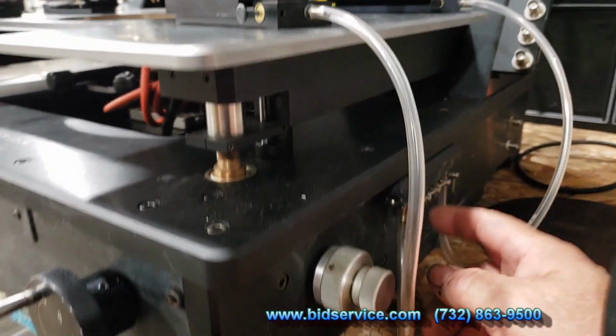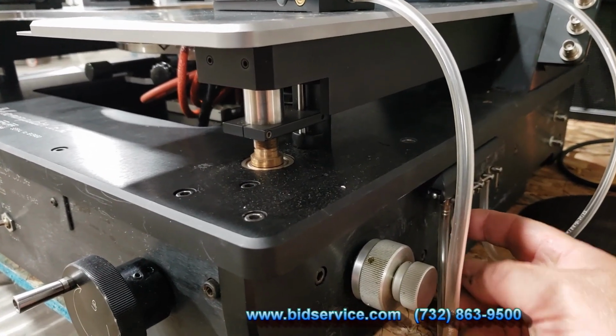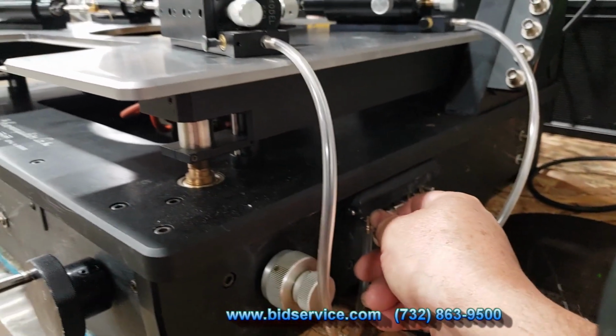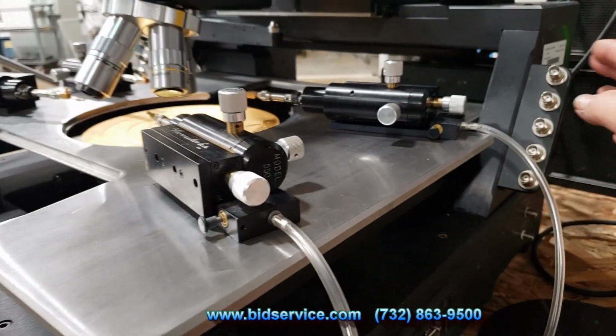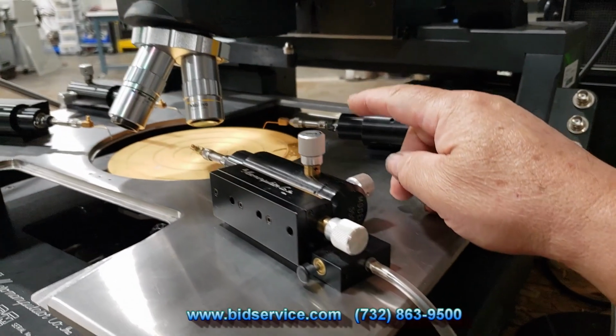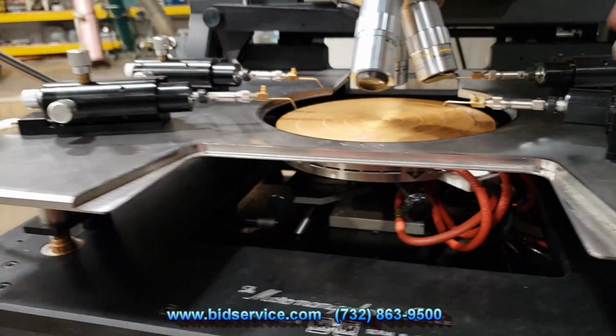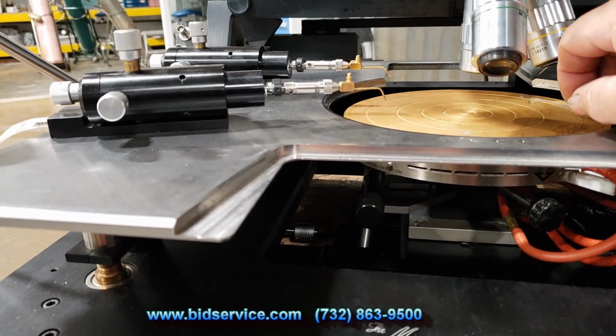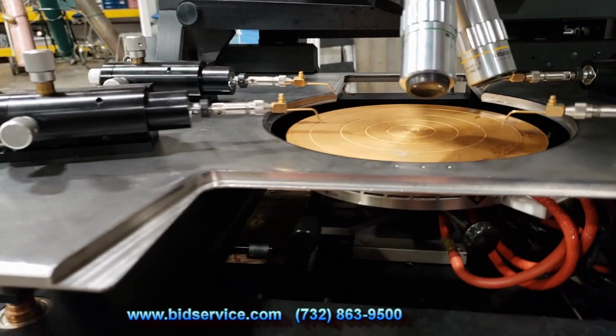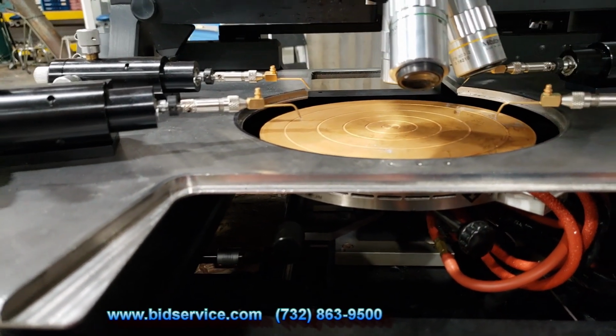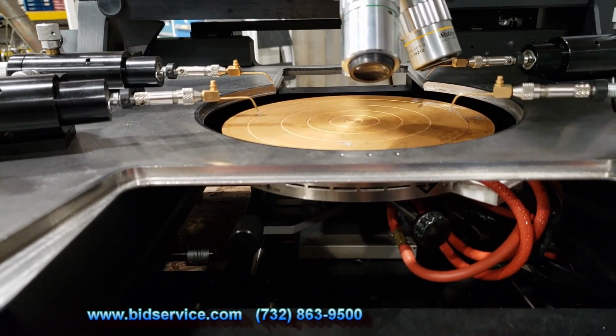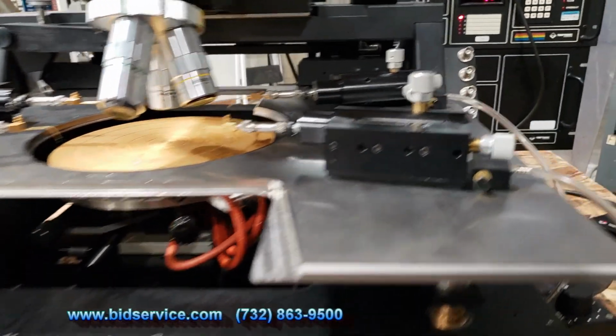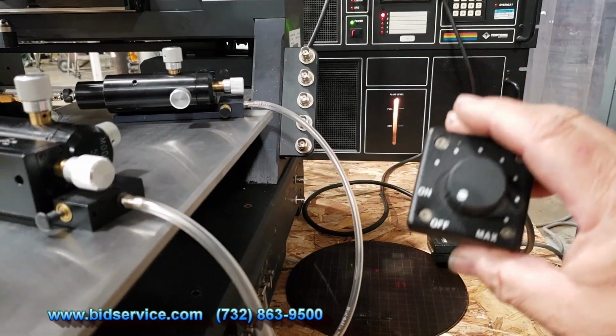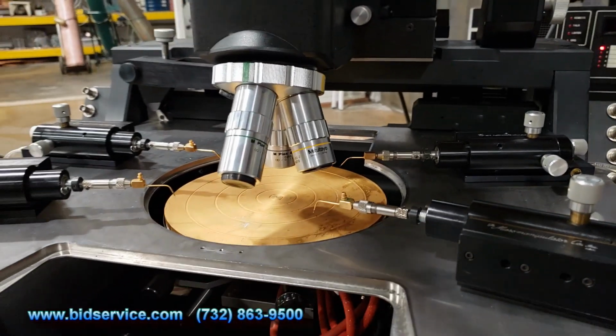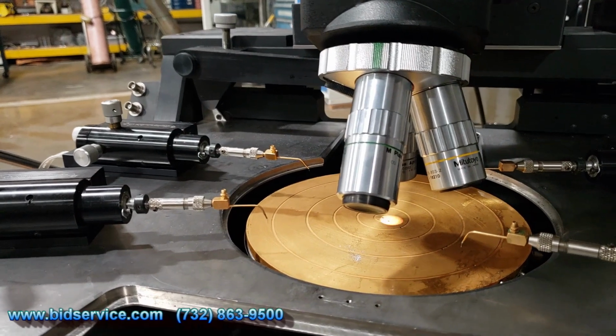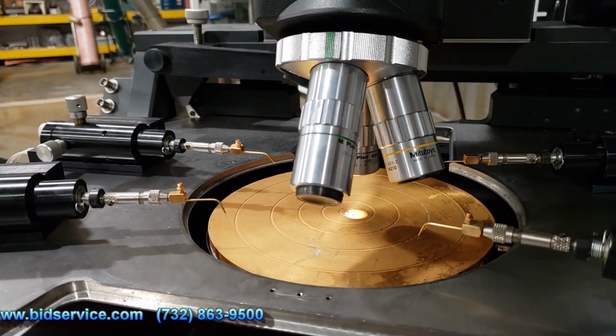On the sides here you have your vacuum control, vacuum valves for your probe stations, and then you have your BNC connectors to the probe heads themselves. These probers do have some kind of used probes on them, but they are probably shot and you'll have to get your own. Now over here is your controller to your microscope lamp. I will turn it on, and you can see that it turns on the chuck, and it's also adjustable.